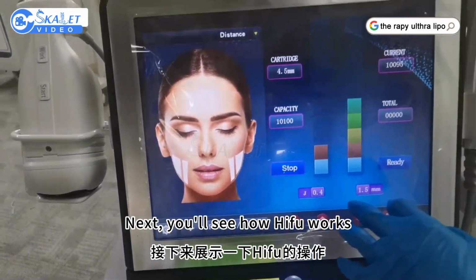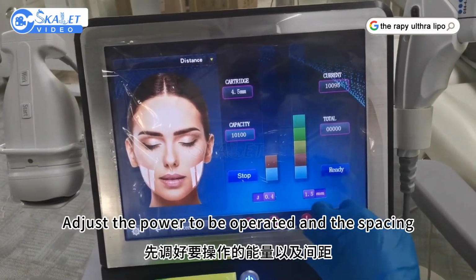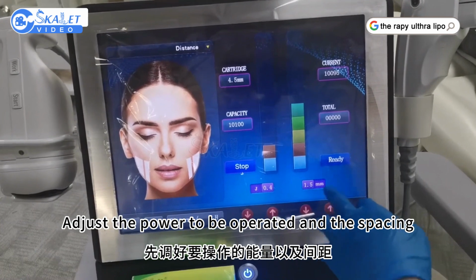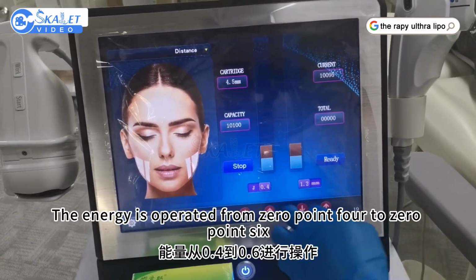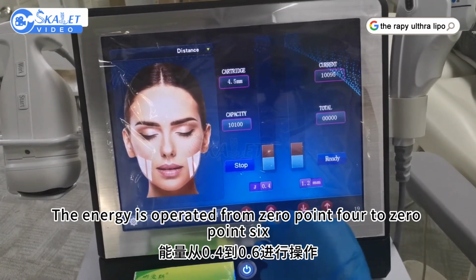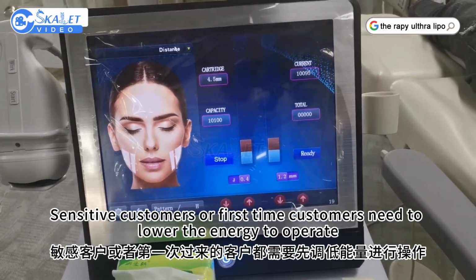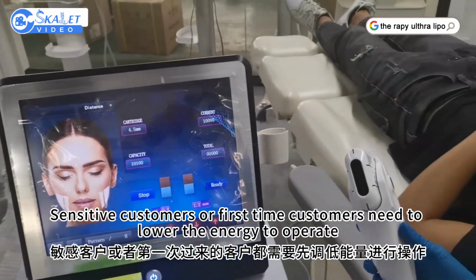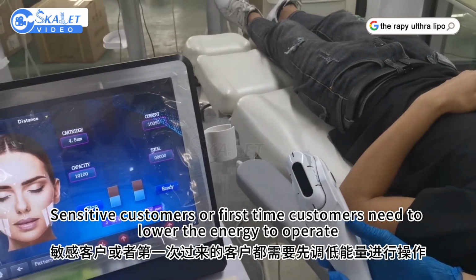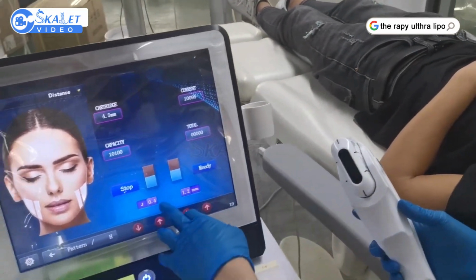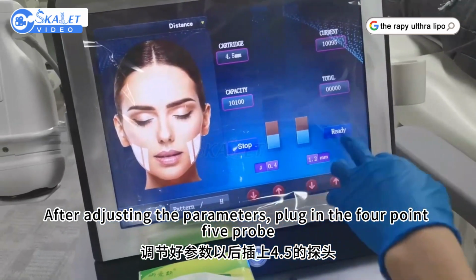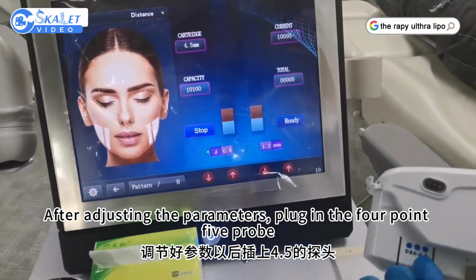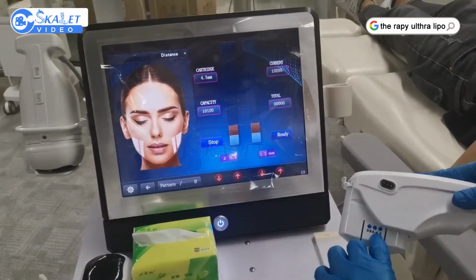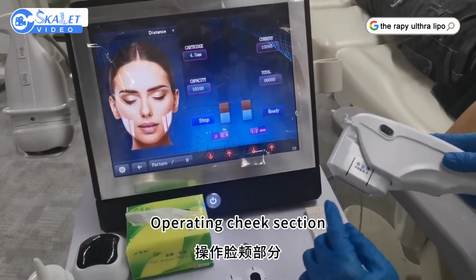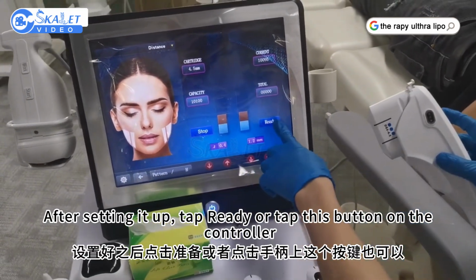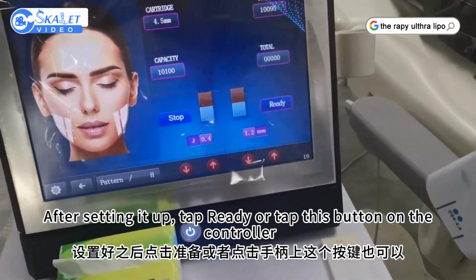Next, you'll see how HIFU works. Adjust the power to be operated at the spacing. The energy is operated from 0.4 to 0.6. Sensitive customers or first-time customers need to lower the energy to operate. After adjusting the parameters, plug in the 4.5 probe. Operating the cheek section. After setting it up, tap ready or tap this button on the controller.